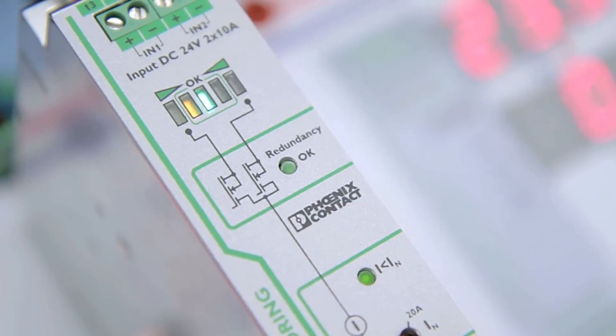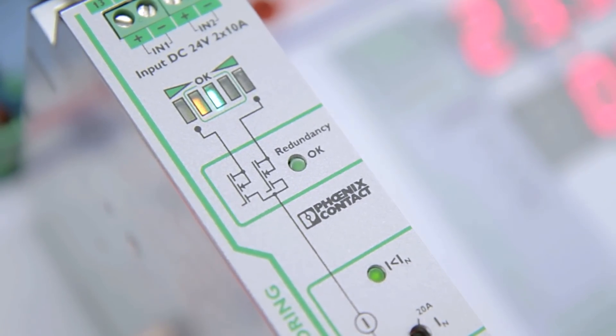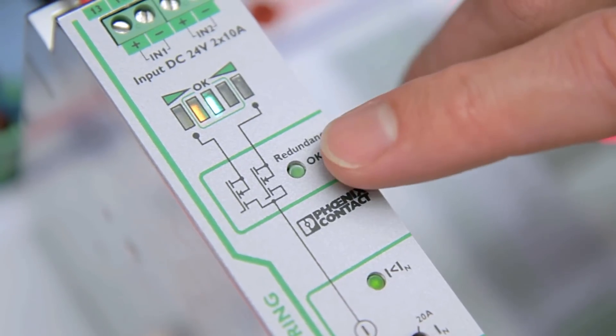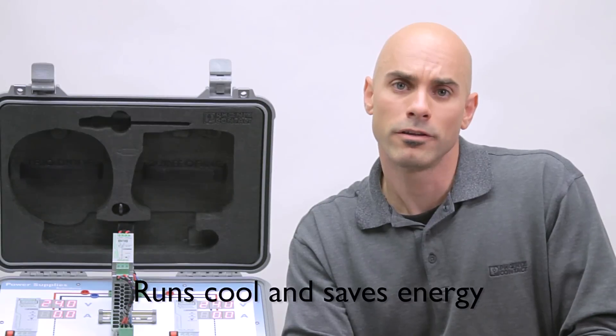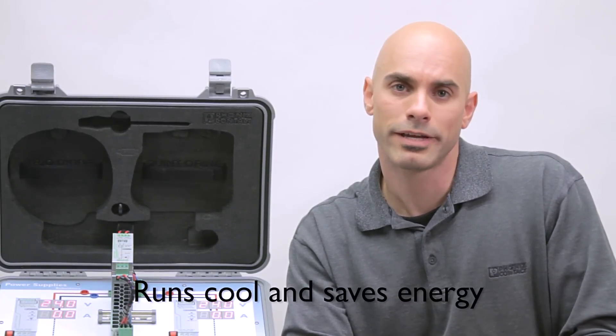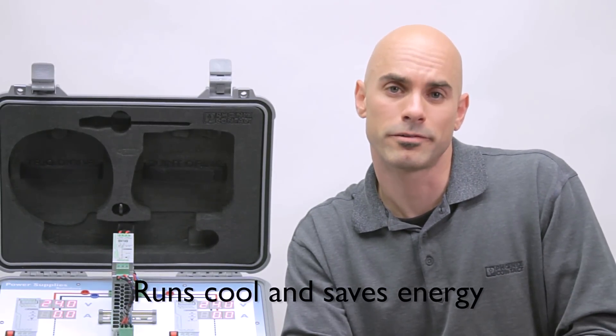You may notice that this device has no heat sink and the face of the module has a symbol for MOSFET. That's because the Quint O-Ring redundancy module is solid state and uses MOSFETs instead of standard silicon diodes for decoupling. So, with O-Ring, you will save up to 70% on the energy used, as compared to standard redundancy modules.